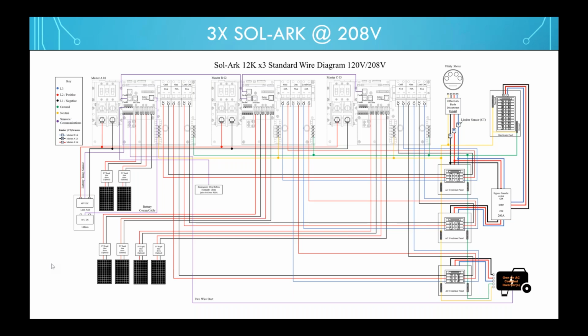Yeah, and sticking with the theme that the Sol-Ark inverter is very powerful, very capable and very versatile, let's talk about 208 volt for a minute. I've done a lot of commercial and industrial solar in my day, behind the meter, a lot of 208 volt, a lot of 480 volt, but this is 208 volt. The 208 volt commercial buildings that I like are banks, pharmacies, CVS pharmacy, Walgreens pharmacy kind of thing, gas stations, or smaller food marts. Not the really big ones. The really big ones are probably going to go up to 480 volt, but it's the smaller food marts.